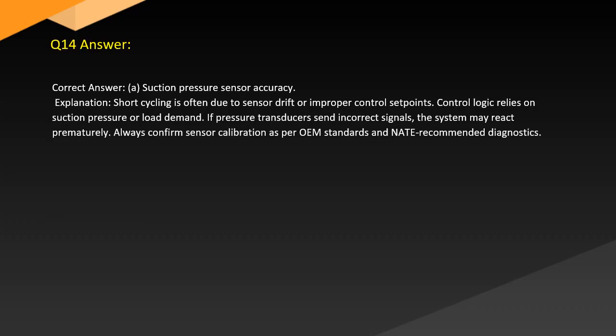Answer. Correct answer: A. Suction pressure sensor accuracy. Explanation: short cycling is often due to sensor drift or improper control set points. Control logic relies on suction pressure or load demand. If pressure transducers send incorrect signals, the system may react prematurely. Always confirm sensor calibration as per OEM standards and NATE recommended diagnostics.